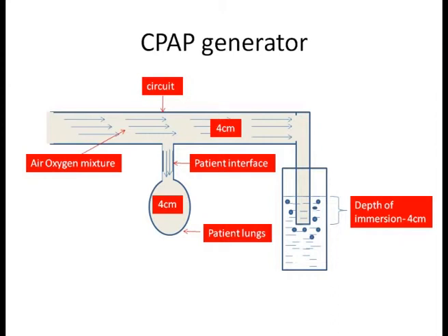Excess bubbling in the bubble chamber only means either there is wastage of gases or there is a turbulent flow which might inadvertently give high pressures in the circuit and also high pressures delivered to the patient.